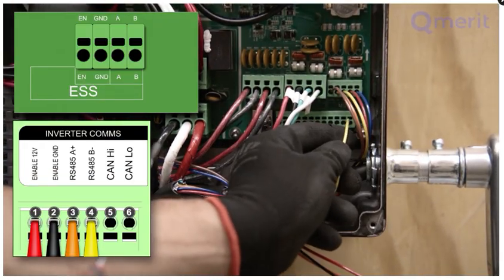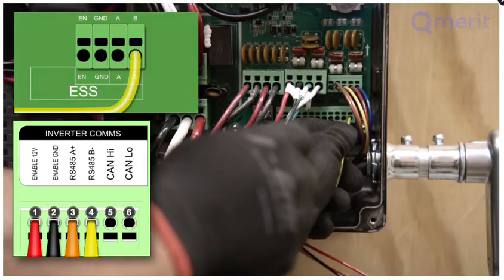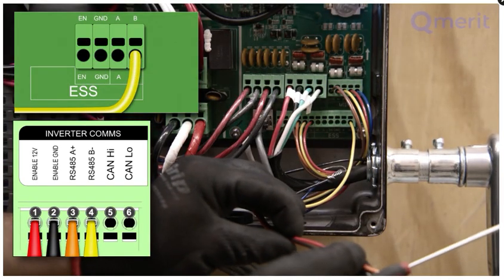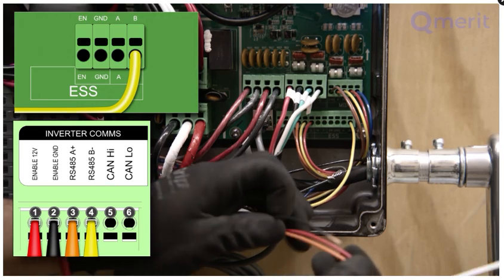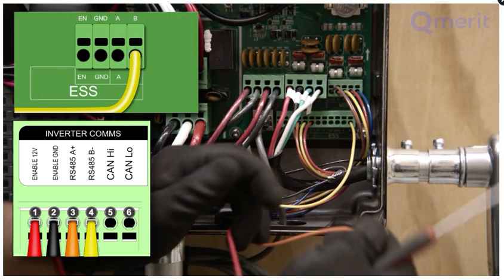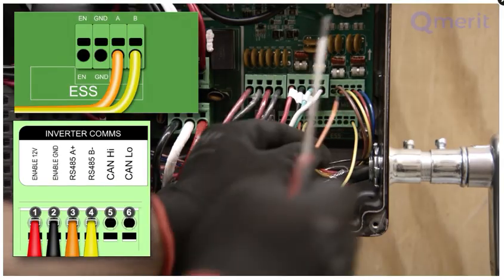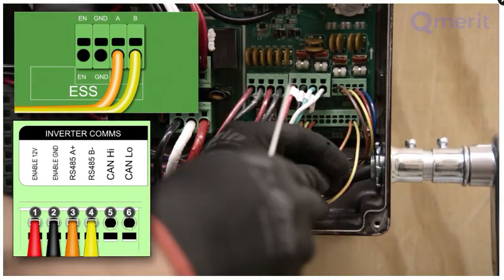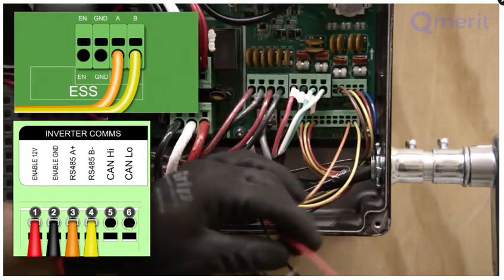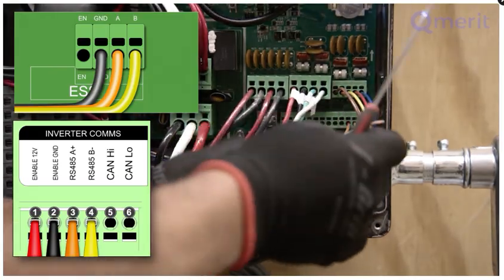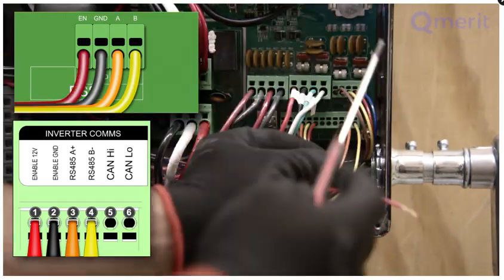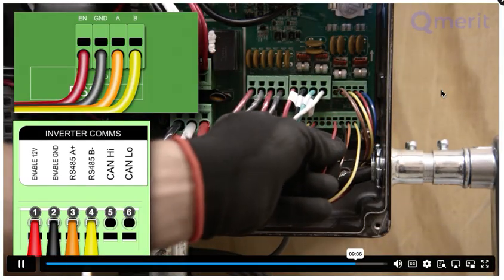Using a screwdriver, press the slot above to release tension and slide the wire into the slot. The yellow wire goes to the B slot, matching the RS485B- on the BCU. The orange wire goes to the A slot, matching the RS485A+ on the BCU. The black wire goes to the ground slot, and the red wire goes to the EN slot, matching the Enable 12-volt slot on the BCU.